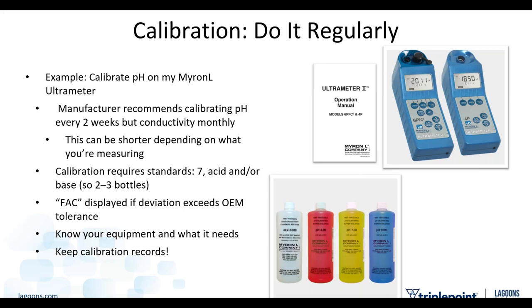So that interval can be longer or shorter. It really depends on what you're measuring, what you're using, what the OEM says. For the Myron L, for pH, I was typically using two or three different standards: pH 7, neutral, an acid and a base. If I saw FAC on the screen, that said the deviation exceeded the OEM tolerance. I either needed to calibrate to a lower number and repeat the calibration a couple of times, or I had to replace the sensor or the meter entirely. Again, if you're not doing this, you don't know that your meter is experiencing problems. This is how you ensure that your equipment is operating properly. Know your equipment, know what it needs, keep records, very important.